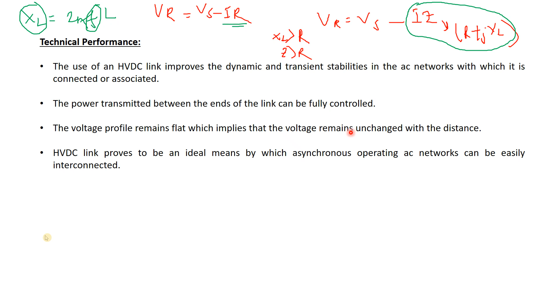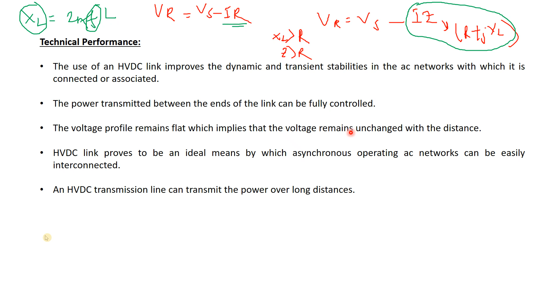How? Just at the HVDC receiving side, you convert the HVDC back to HVAC using an inverter, and a set frequency will be given by the inverter, and then it will be connected to the three-phase induction motor or three-phase synchronous motor. So there is no concept of synchronism. Okay, so any asynchronous machine can also be connected to an HVDC link. An HVDC line can transmit power over long distances because it has less power loss.